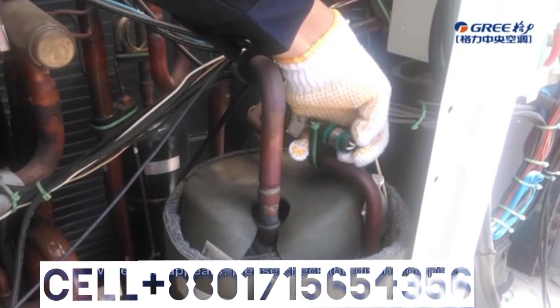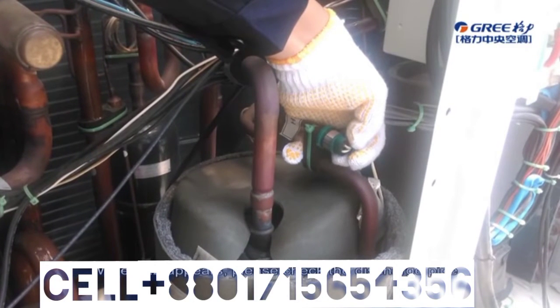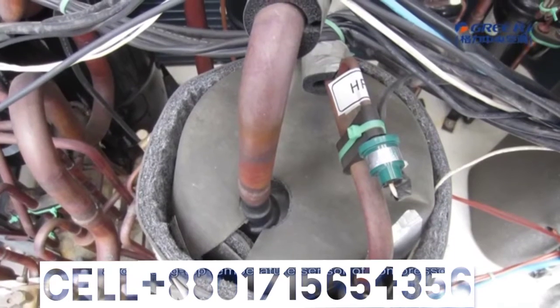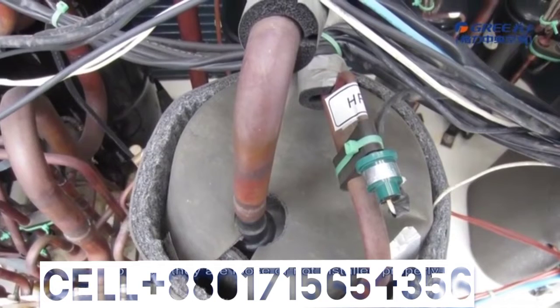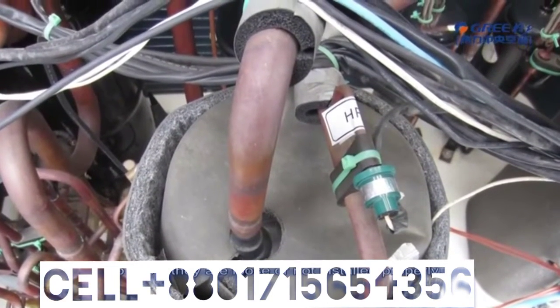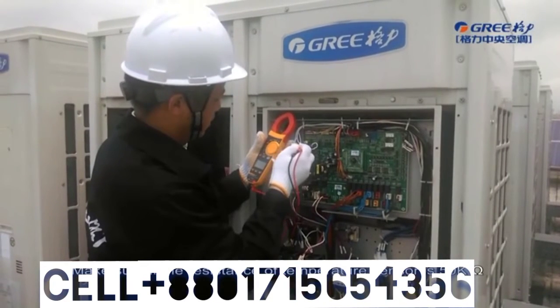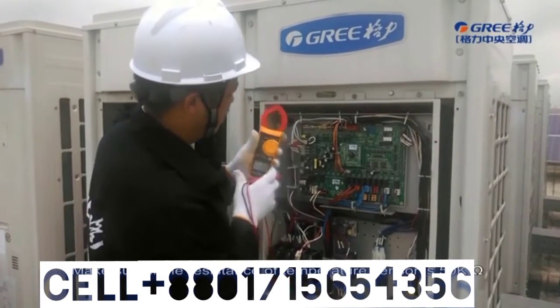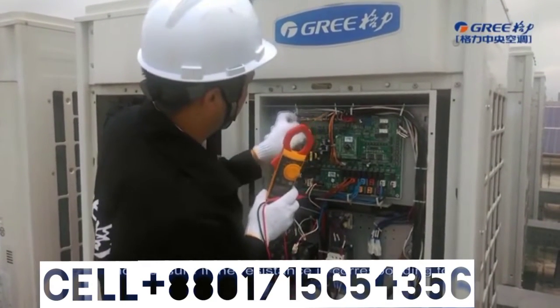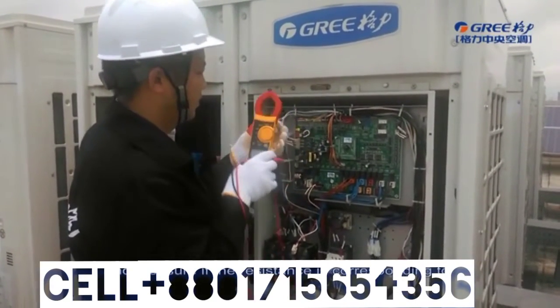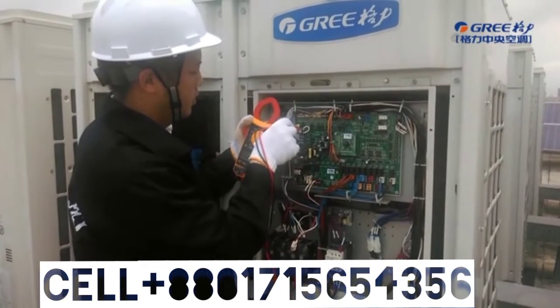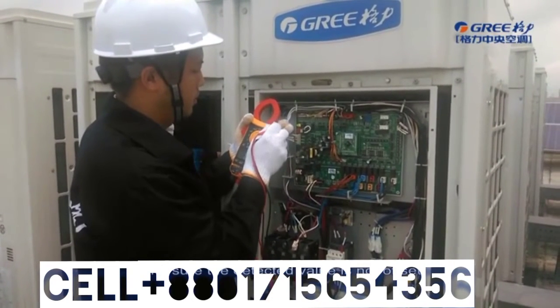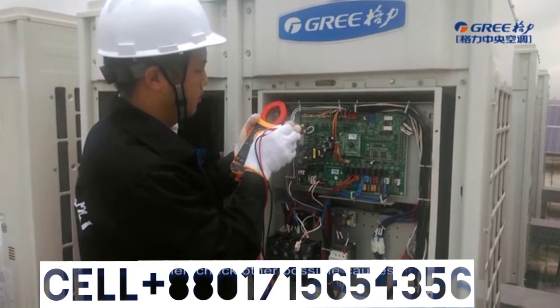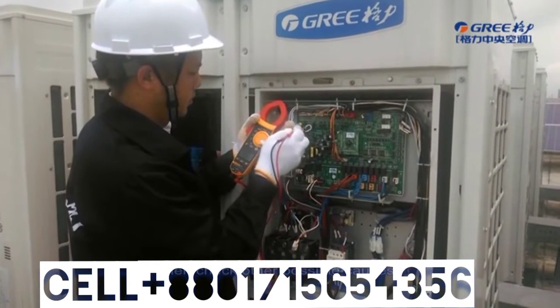When E2 appears, please check the discharge pipe and casing top temperature sensor of the compressor to see if they are loose or not installed properly. Make sure if the resistance of temperature sensor is 50 k ohm and measure if the resistance is corresponding to the actual temperature. Make sure the detected value is not offset, then check other possible causes.